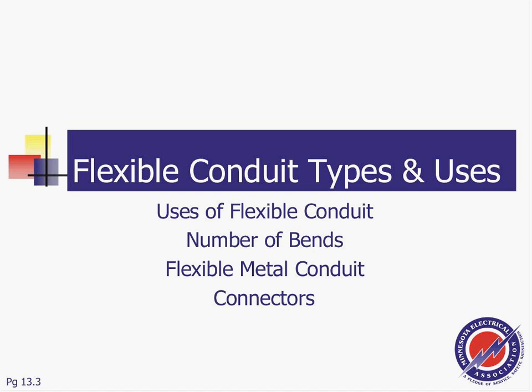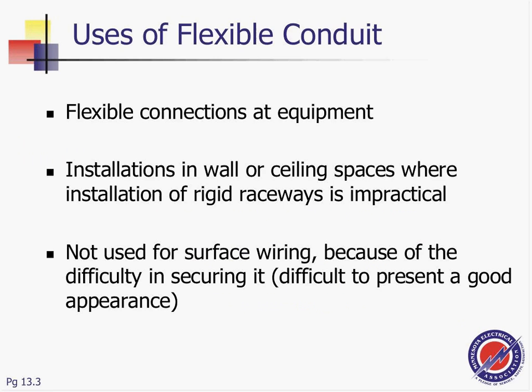Okay, before we start, we're going to start with the flex. I have a couple of things here. We're going to talk about where you use the flex, the number of bends, flexible metal conduits, and connectors. That's basically what we're going to do. We'll go ahead, guys, and talk about flexible conduits. There are a few things you have to know about them. Flex conduit, Joe, is not your conduit of choice when it comes to wiring the whole building. The most important thing about flexible conduits, metallic, non-metallic, and liquidtight, is connection to equipment. This is the key point. It's not meant to wire the whole building with, though you can if you want to. It's not the wiring method, put it this way.